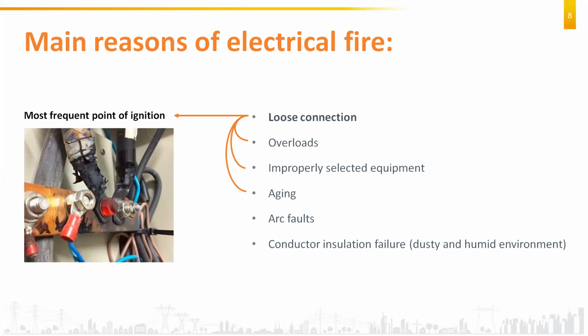Arc faults normally occur because of rodents, because of some moisture coming into the environment, or some equipment failure, right? These are the accidental reasons for the occurrence of an arc flash. What is the electrical reason for the occurrence of an arc flash? If you guess it or if you know it, it is a loose connection. How does it happen? In case of a loose connection, the joint may get heated so much that the conductor or the bus bar may melt, leading to an arc flash. Okay, so the majority of electrical incidents have somewhere a small link with loose connections.